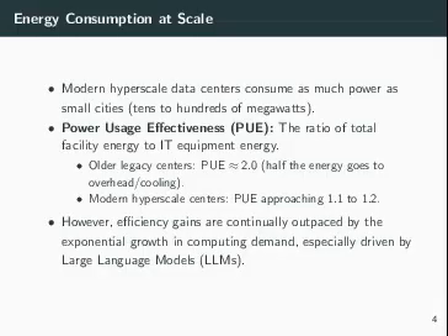Modern hyperscale data centers consume as much power as small cities, scaling into tens or hundreds of megawatts. We measure facility efficiency using power usage effectiveness, or PUE, the ratio of total facility energy to IT equipment energy. Older legacy centers had a PUE around 2.0, meaning half their energy went strictly to overhead and cooling, while modern hyperscale facilities approach 1.1 to 1.2. Unfortunately, these efficiency gains are constantly outpaced by the exponential growth in computing demand, particularly driven by large language models.